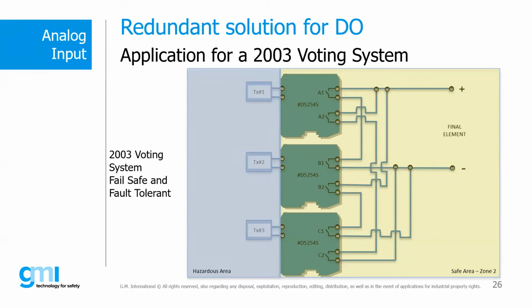I repeat, this type of logic would be possible in another way only by using a PLC system with redundant cards, having a considerably higher cost. This system allows us to achieve a high SIL3 safety standard with high process availability.